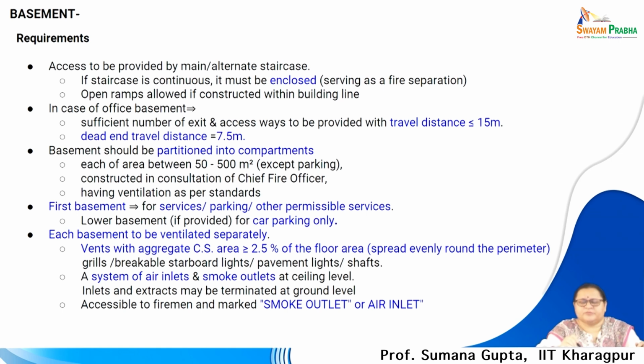Now, coming to the basement. Since the lift is not connecting to the basement, and the basement houses various services in high rise buildings, such as the AHU, laundry and boiler service, these are areas from where fire can also start. So, the basement has to be specially or separately treated with its own vents, with aggregate cross sectional area, all of which are mandated in the NBC. Vents with aggregated cross sectional area of more than 2.5% of the floor area should be there. Smoke outlet and air inlet should be separate. So, a lower basement and a higher basement, if present, should be connected with venting to the outside.